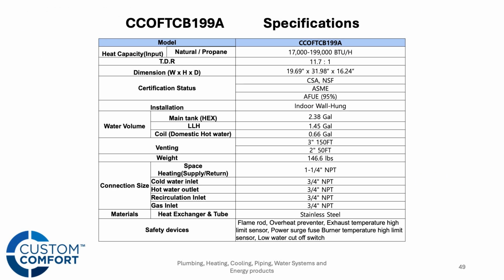So just running through some additional specs on the boiler as well, right? Talked about a lot of this, the turn down ratio, the input, the water content on this. The one downside of this boiler, if there are any, is potentially the weight. It's a heavy boiler. It's 146 pounds. So unless you're the Incredible Hulk, you're probably looking at 2 people to hang this on the wall.